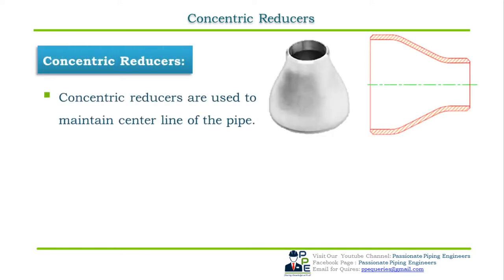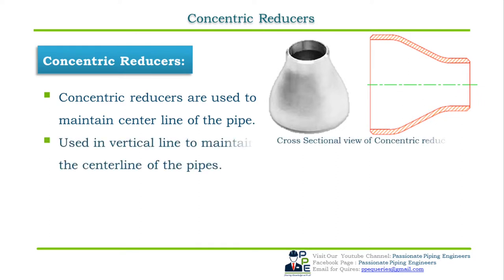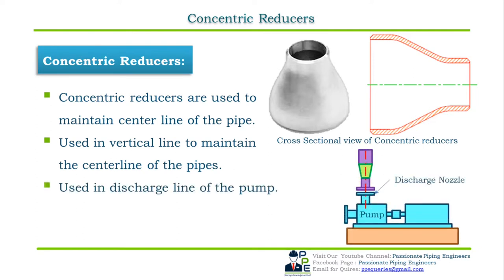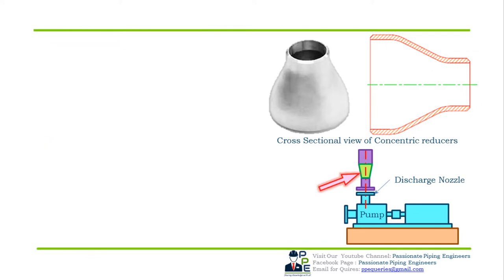Concentric reducers are used to maintain the centerline of the two different line sizes. As seen in the cross-sectional view, there is only one centerline that intersects both the large and small pipe diameters. Concentric reducers are most commonly used in vertical lines to maintain the centerline of the pipes, and more commonly used in the discharge line of a pump.